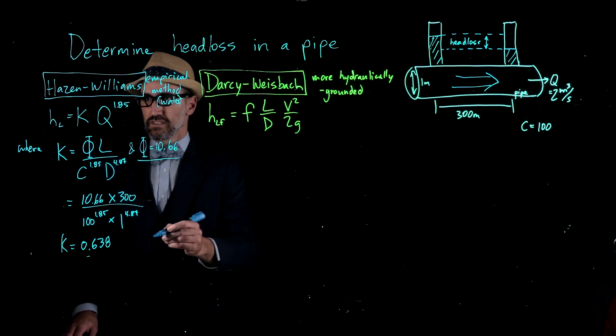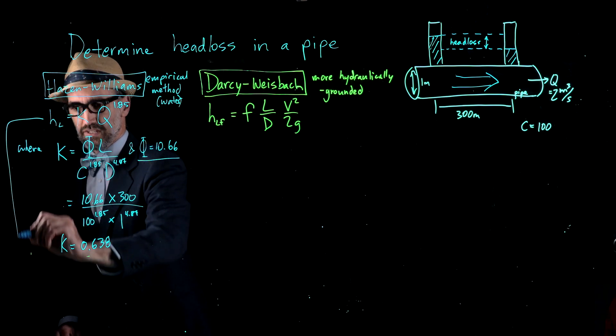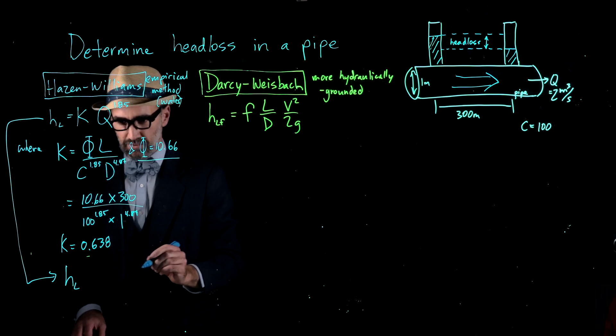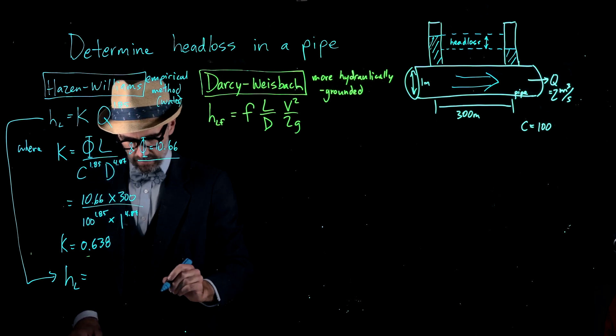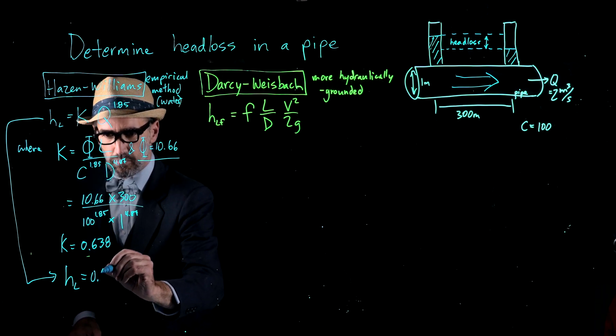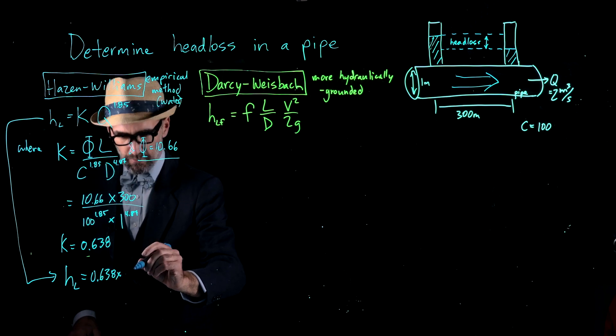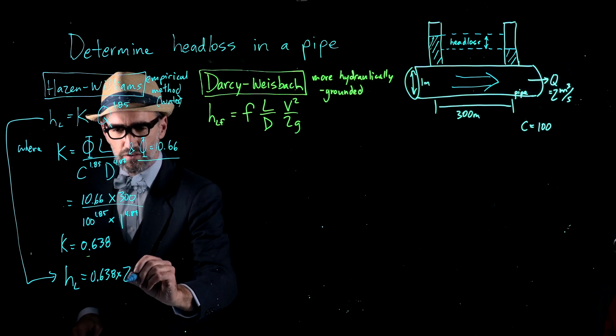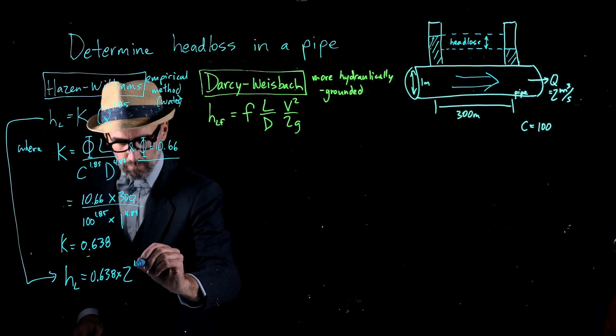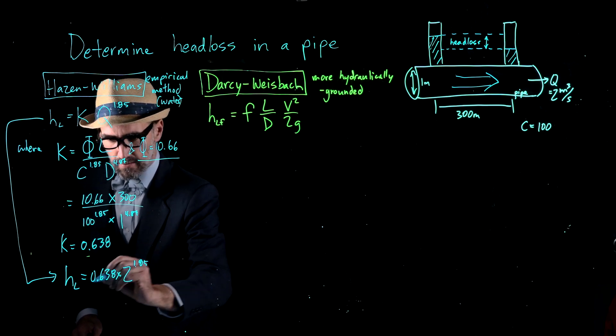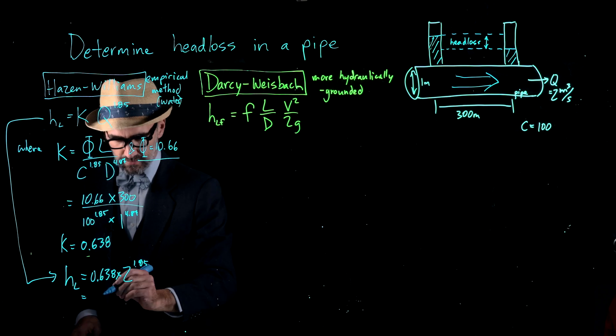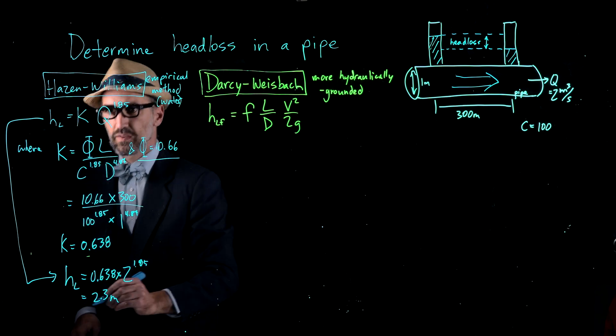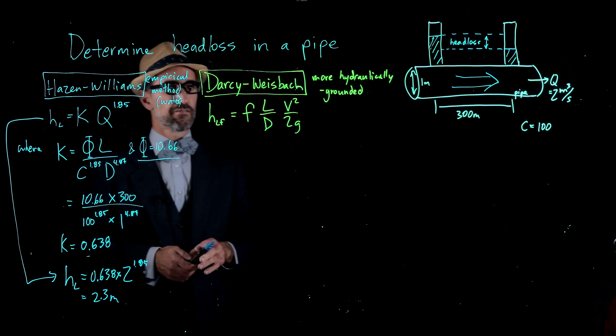We can substitute that into the equation to solve for head loss using the Hazen-Williams methodology. The head loss equals 0.638 multiplied by the flow Q to the exponent 1.85, which results in a head loss of 2.3 meters. That's our first calculation of head loss.